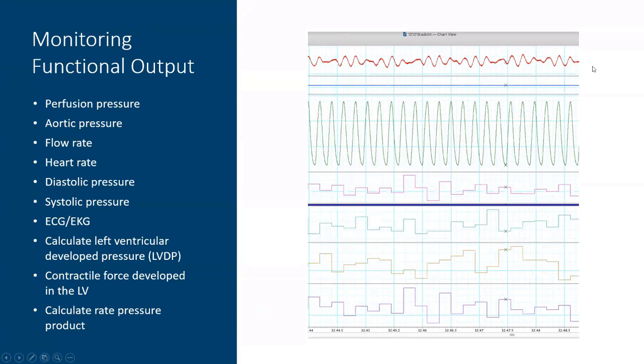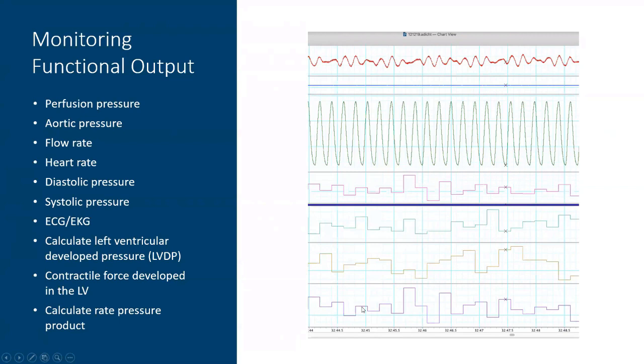Functional outputs we measure include perfusion pressure (also called aortic pressure), flow rate, heart rate, diastolic pressure, and systolic pressure. We also have the capability to record an ECG/EKG, giving an idea of action potential development. Using software algorithms, we calculate left ventricular developed pressure (LVDP) to assess contractile force, and the rate pressure product (RPP) — a mathematical modification of LVDP multiplied by heart rate in beats per minute.